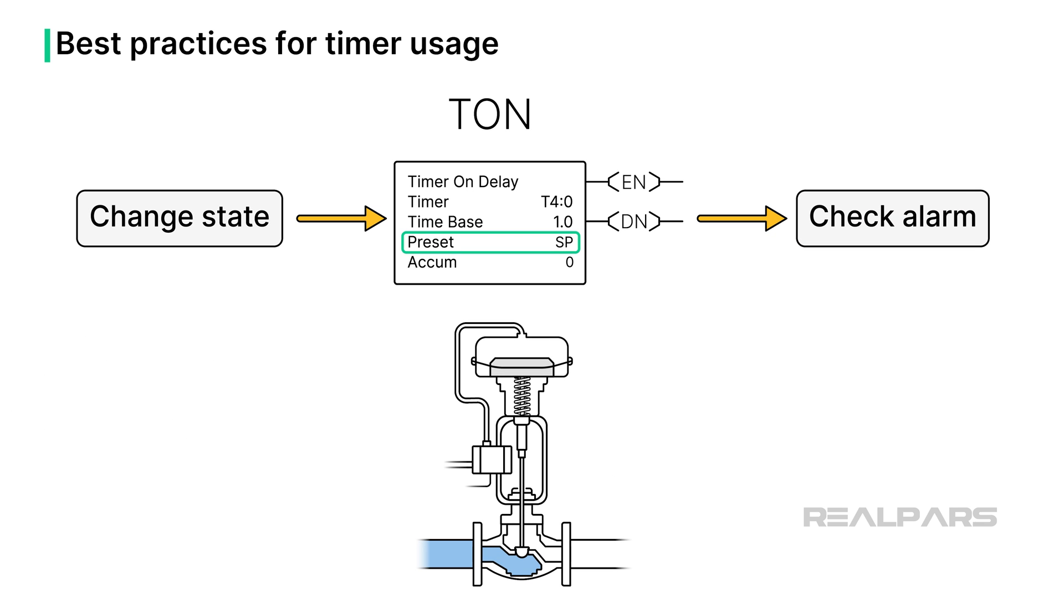Setting appropriate timer presets is very important. If I'm trying to delay the evaluation of a valve position alarm when a change of state is requested, I would want to set the timer to a reasonable value, such as 3 seconds. This allows enough time for the valve to change state without an excessive delay, before an alarm condition is checked.